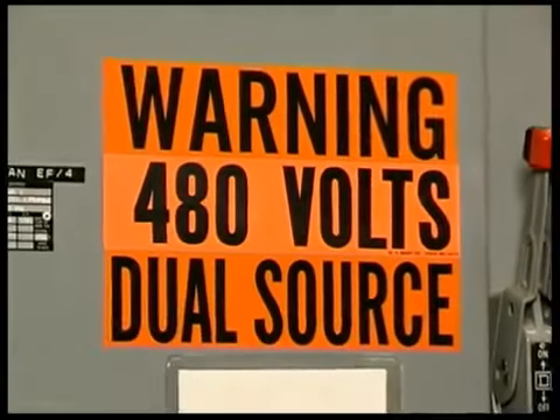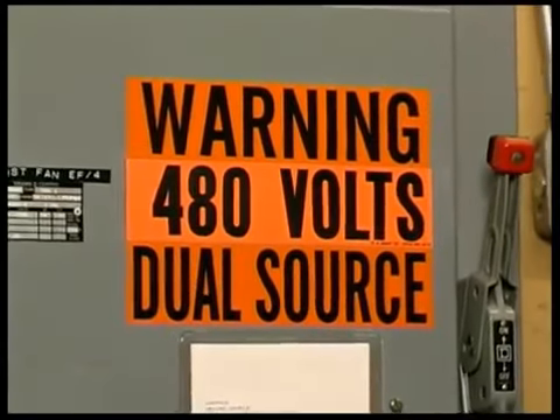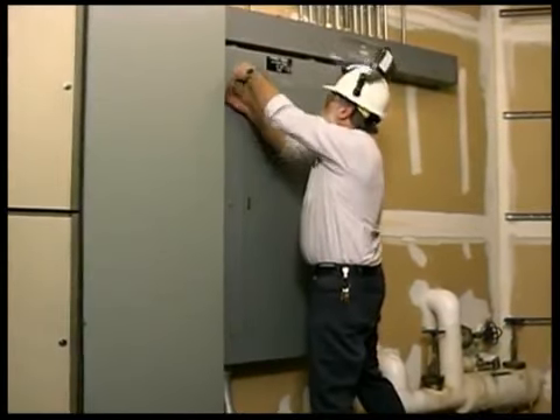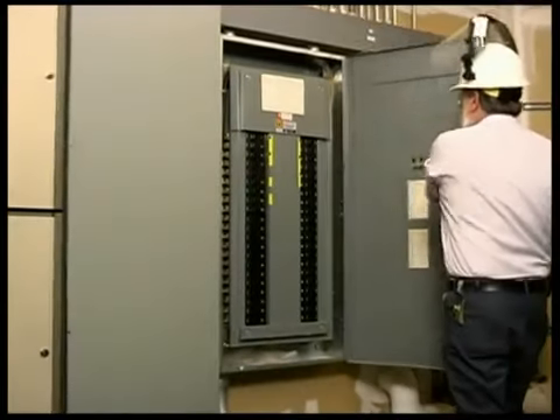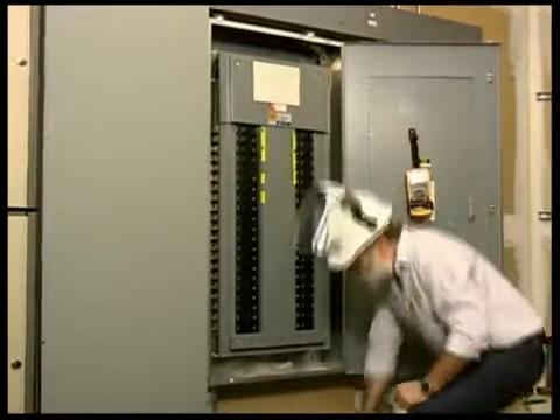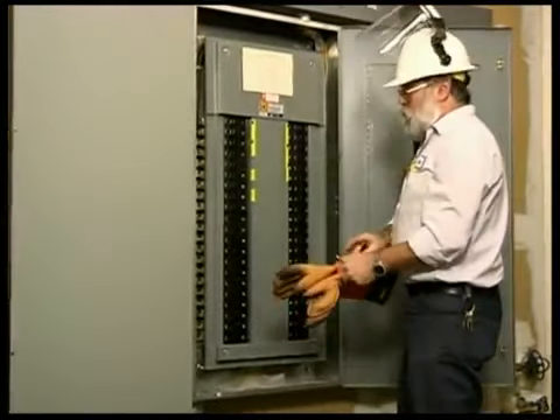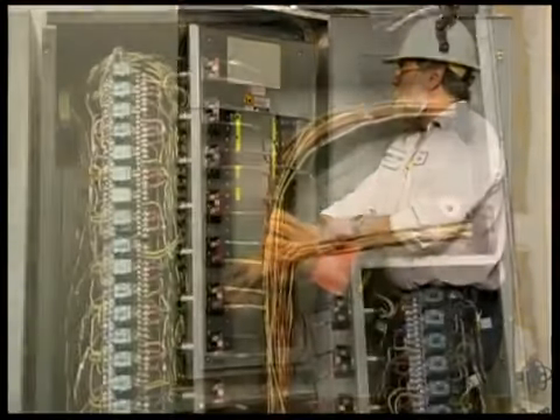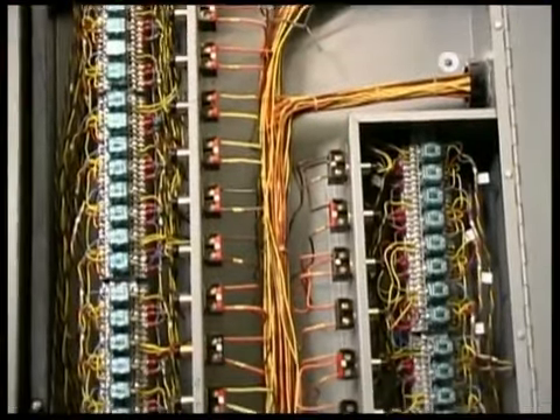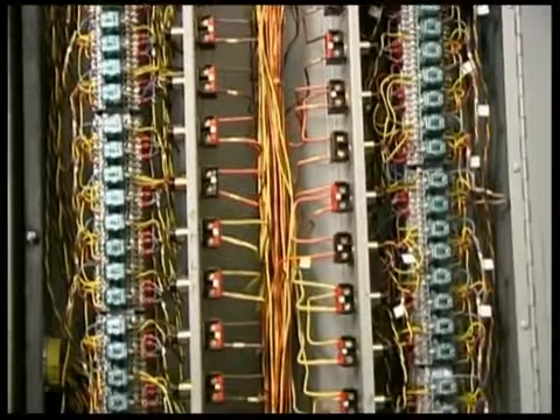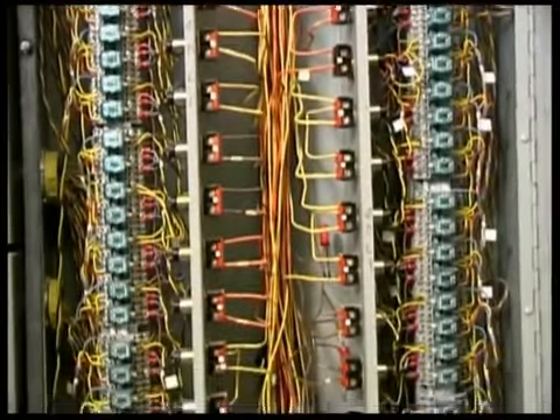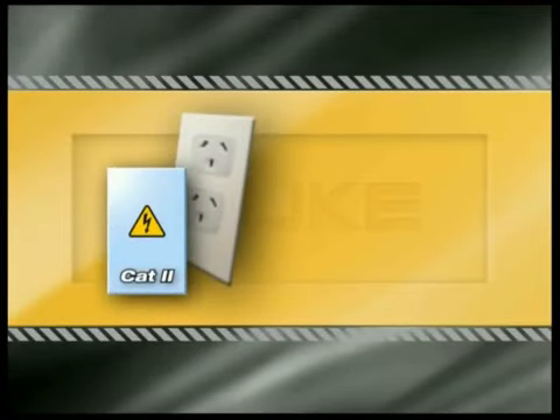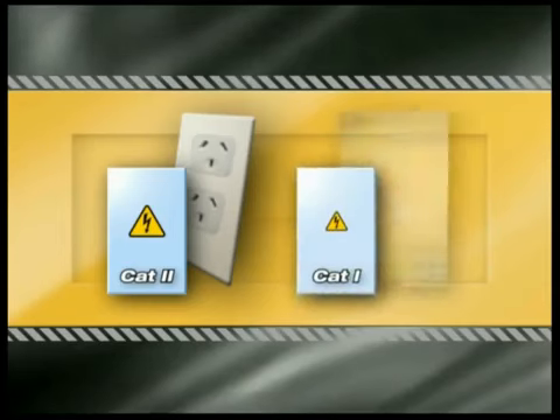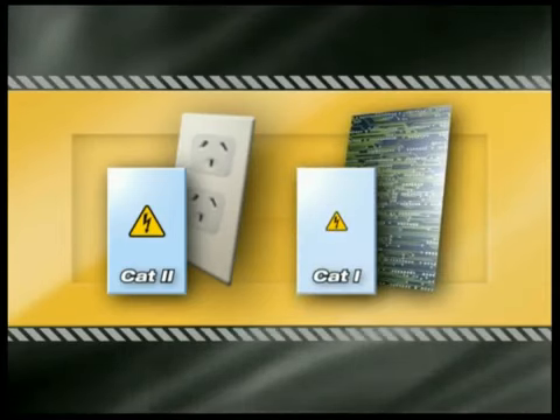The trend to using higher voltage levels in modern buildings has changed the picture and increased the potential hazards. Most electricians work on equipment in a Cat 3 or Cat 4 environment. Many times, people may be working in a Cat 4 environment without even knowing it, and that can lead to real danger. Lower category installations usually have greater impedance, which dampens transients and helps limit the fault current that can feed an arc. Cat 2 covers the receptacle circuit level and 230-volt plug-in loads. And Cat 1 refers to protected electronic circuits.